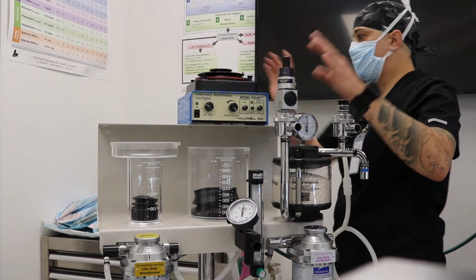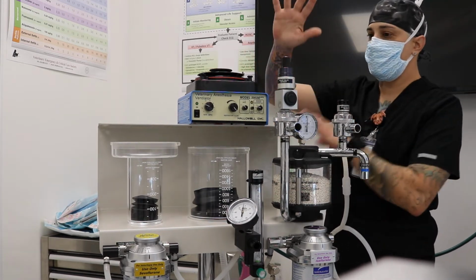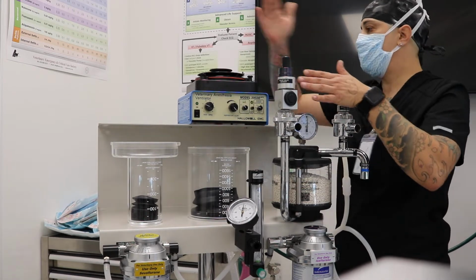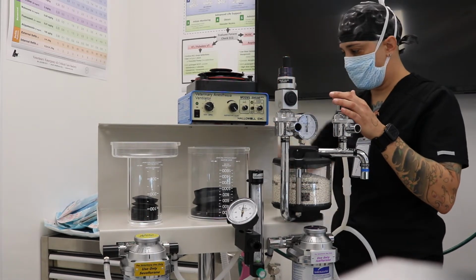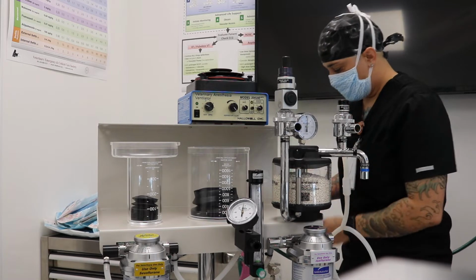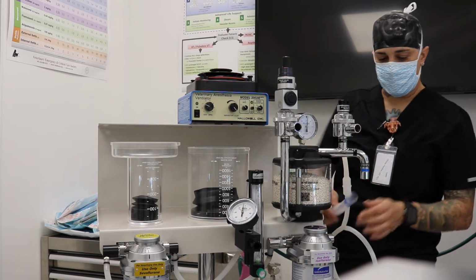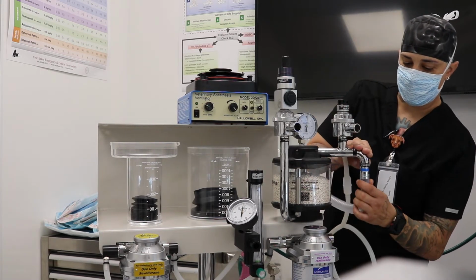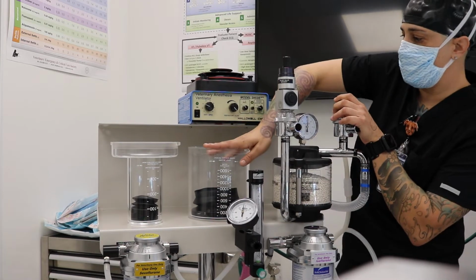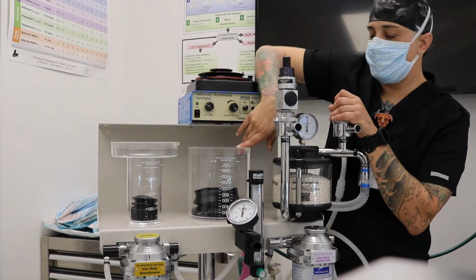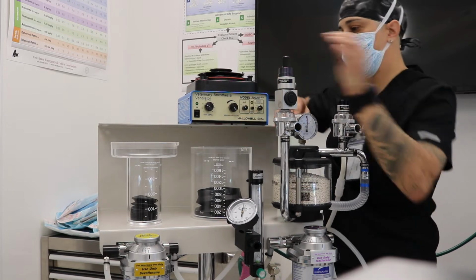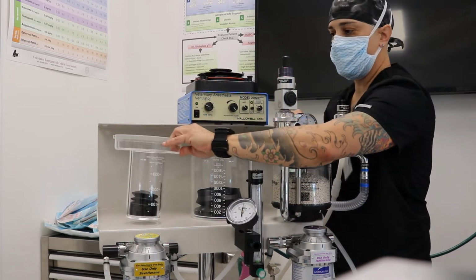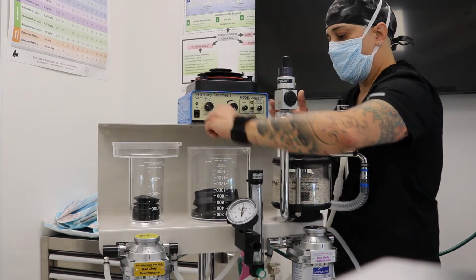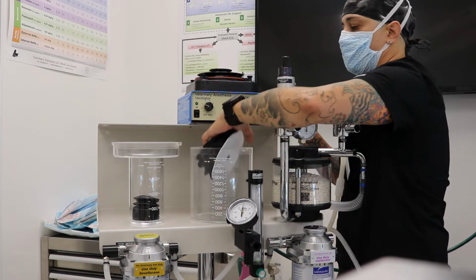Alright, so our exhaust has been connected, taken off of our rebreathing system and connected to our exhaust in the back, down our F-air canister. This is our breathing system, blue. We have it circled blue to blue, becomes our reservoir bag, right? We have our bellows here. Small bellows, large bellows, patient size dependent. I usually do 10 kilograms and under is small. It's up to you, whatever works best for your patient.